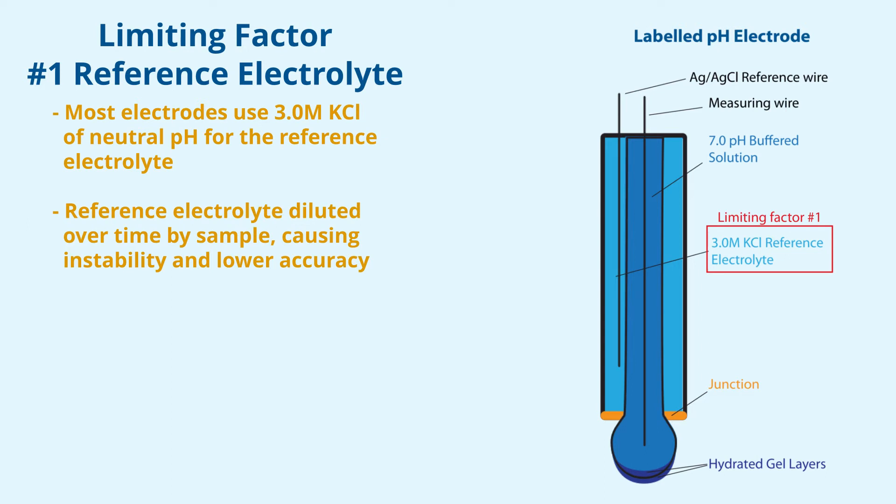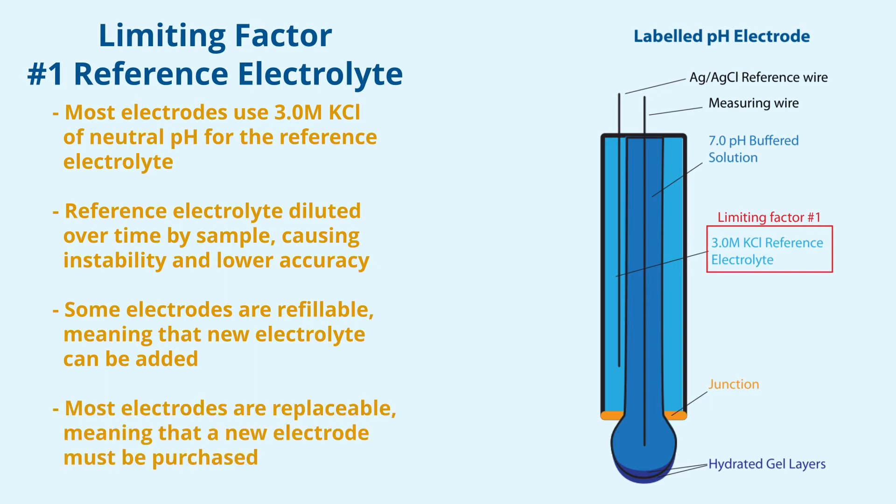Once dilution occurs, either new electrolyte must be added if the electrode is refillable, or the electrode must be replaced depending on the design of the sensor. Using the proper storage solution prevents this dilution so you get the most value out of your pH sensors in the long run.